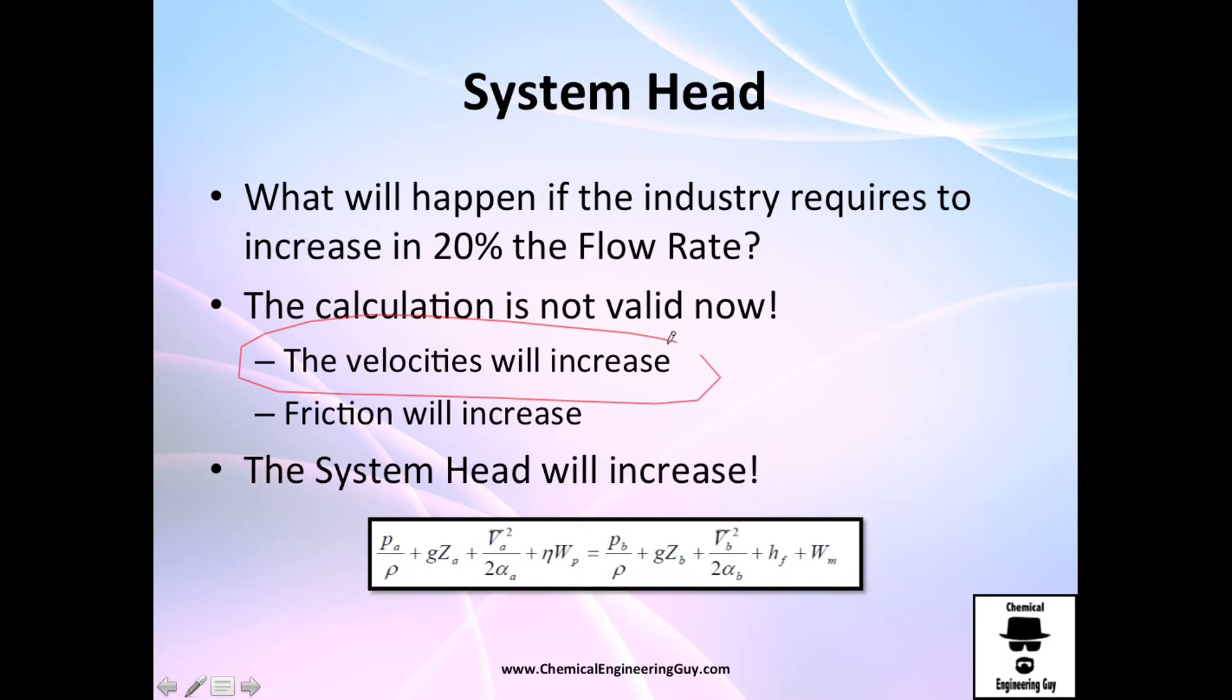So that's interesting. Velocity will increase and friction will increase. So this right here and this right here and this right here will change with respect to volumetric flow rate. And that's what I want you to analyze, think, and think of the curve or the system head. What will happen if we increase Q? Hopefully you get the idea. We're going to increase the amount of requirements of energy.